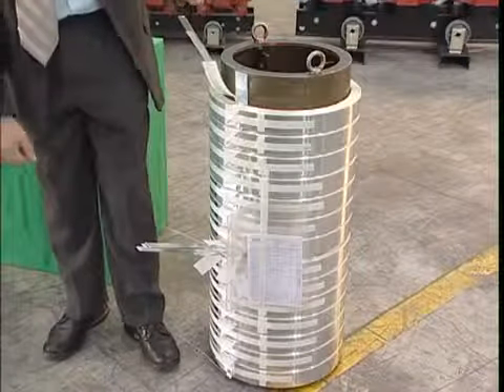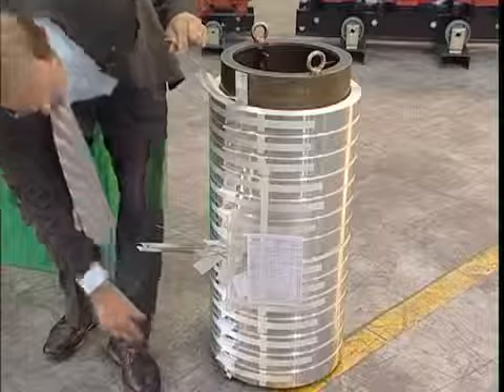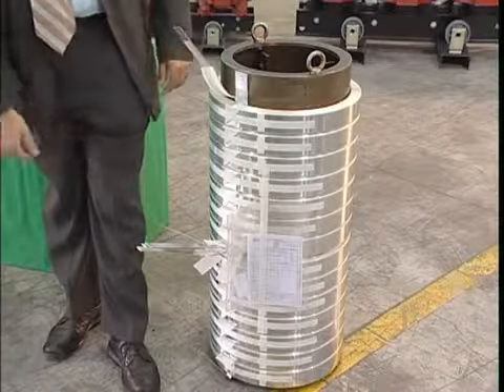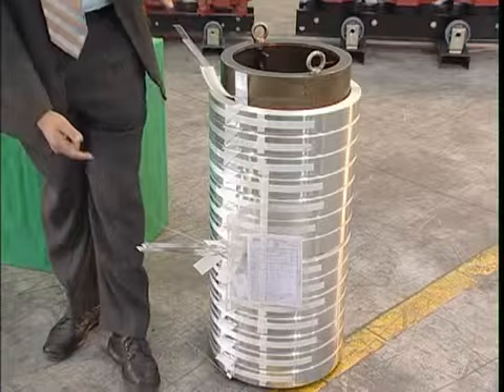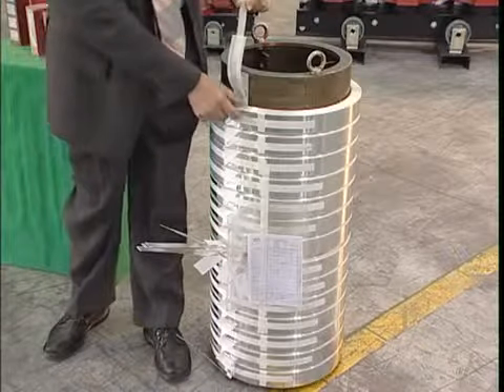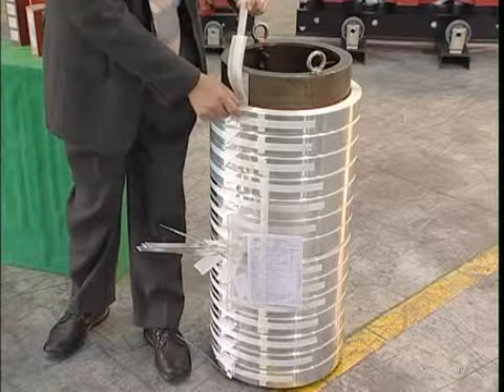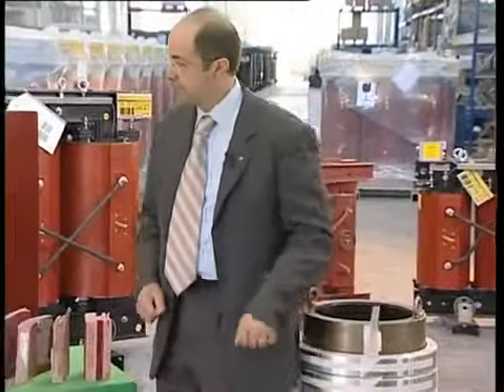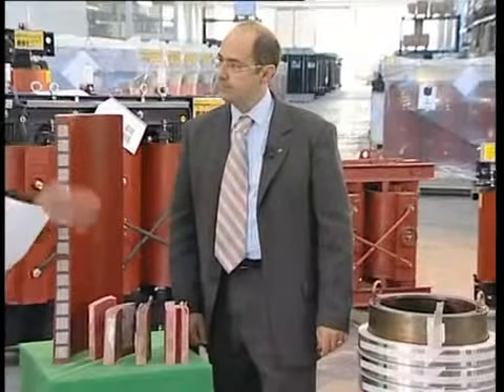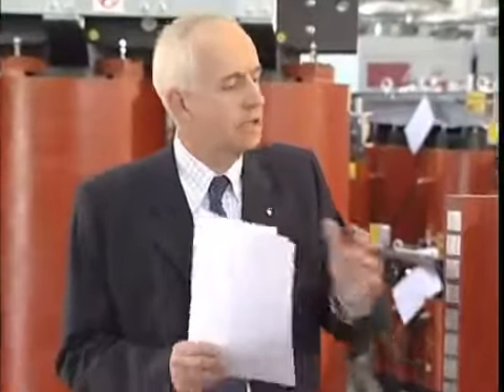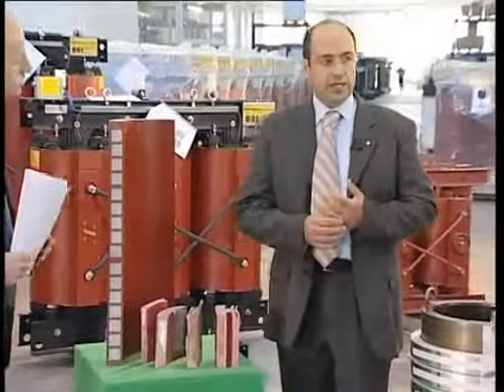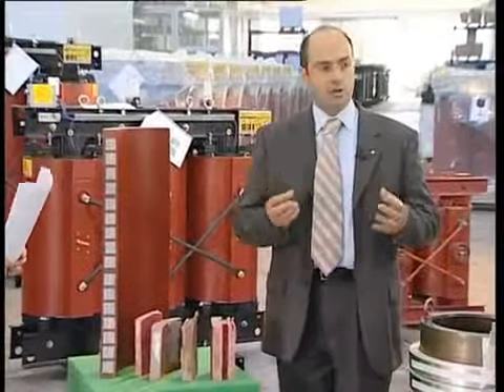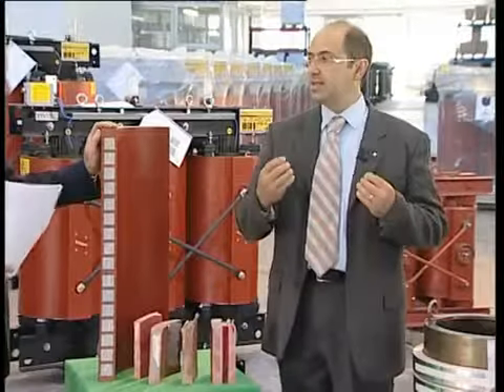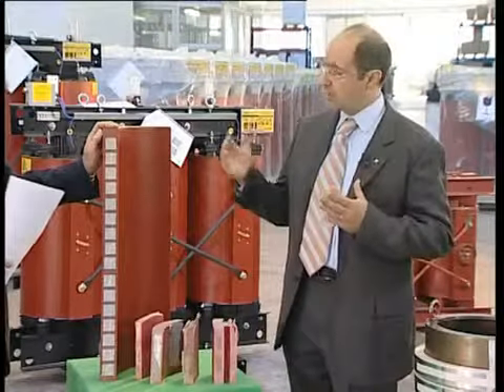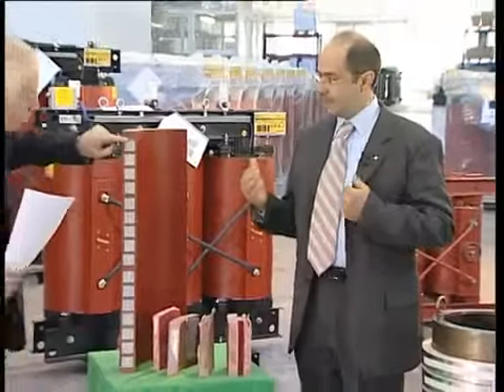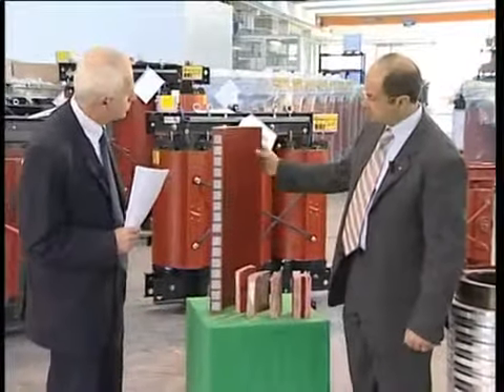We can observe that the voltage applied to the cables of this winding is evenly distributed along the winding's entire height and along each disc's thickness. We can therefore say that in equal insulating conditions, the dielectric stress is constant. Indeed, during the design stage, we are able to determine what the dielectric stress of the entire winding will be throughout its life. And this can be seen by the naked eye looking at this winding.